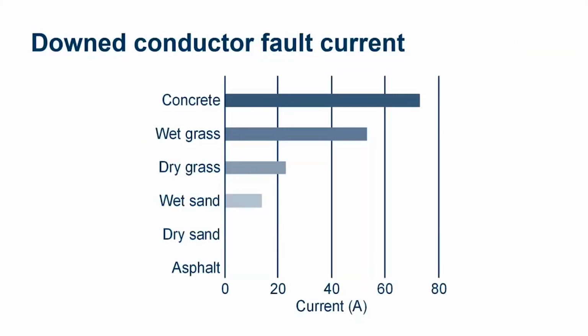But one of the largest influencers of that is going to be the type of surface that our conductor is making contact with. And you can see here some examples of different surface types and typical available fault currents. This is actually taken from some staged down conductor testing that was conducted, and there's a paper available on our website that talks a little bit more about this.